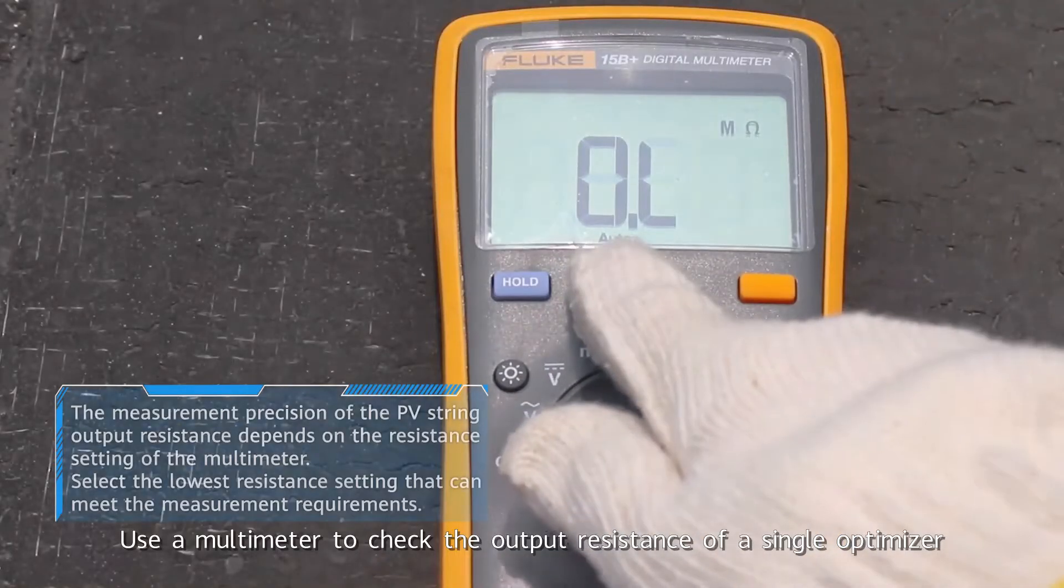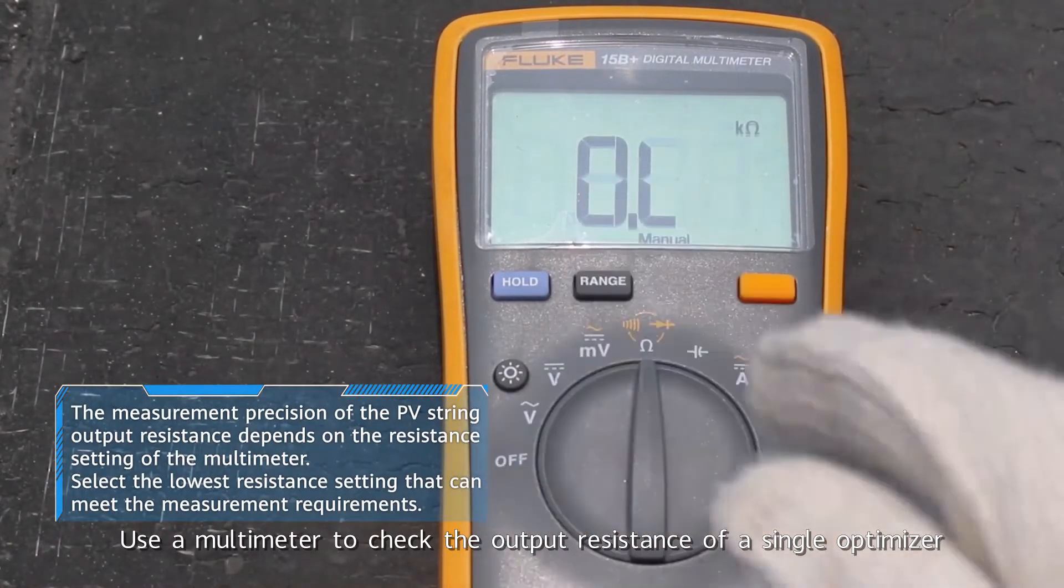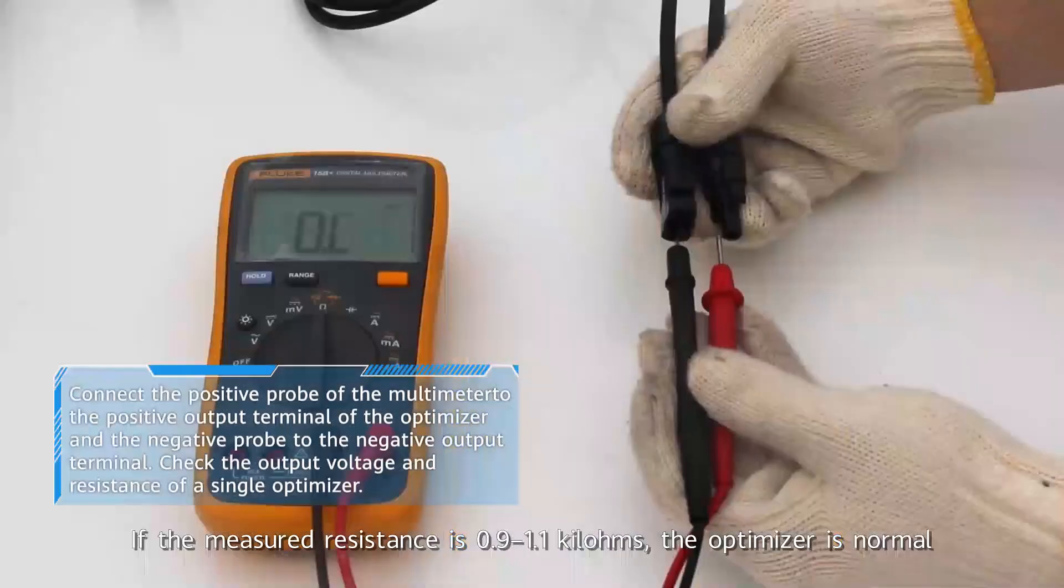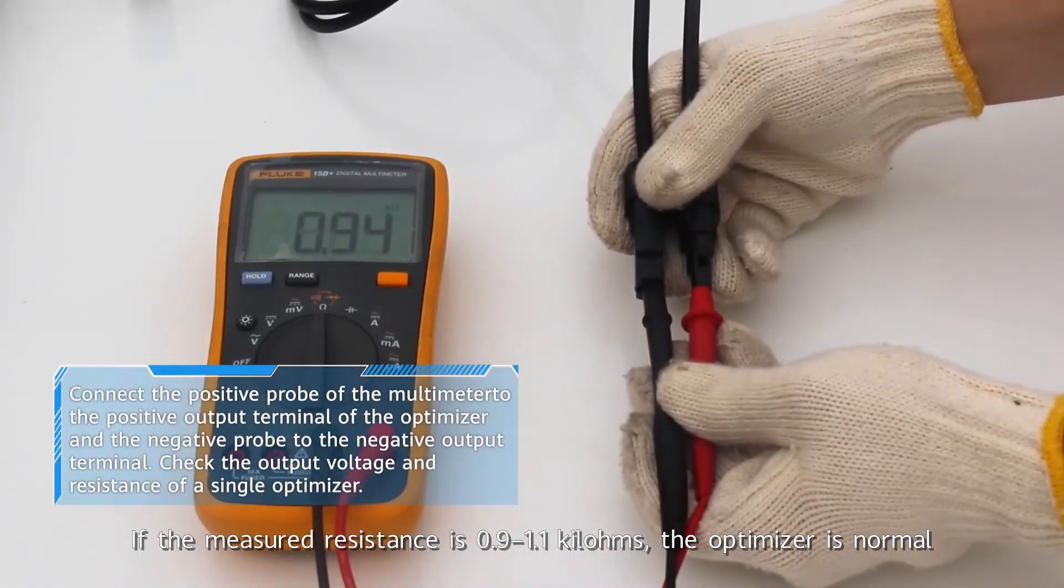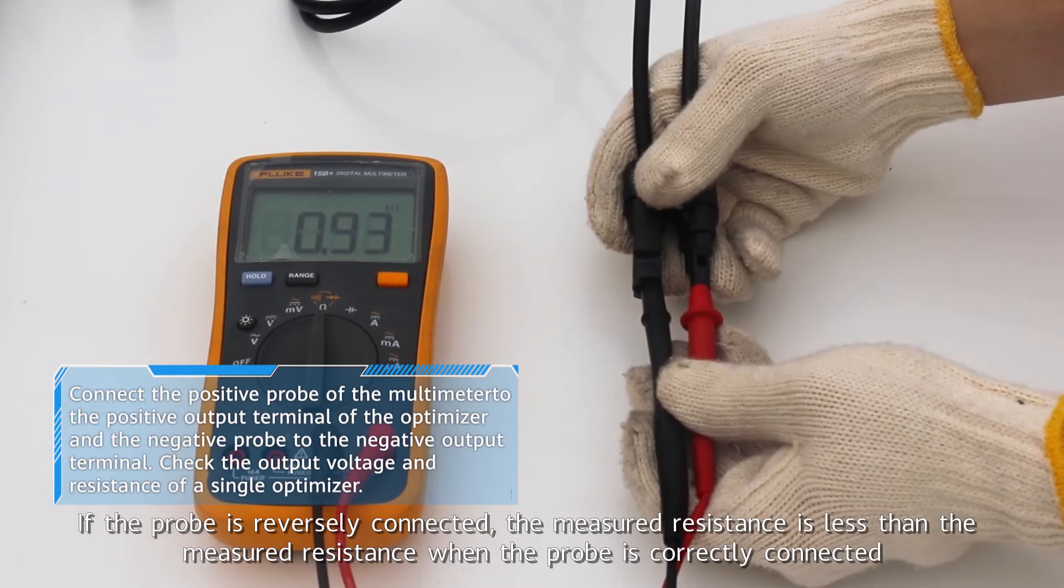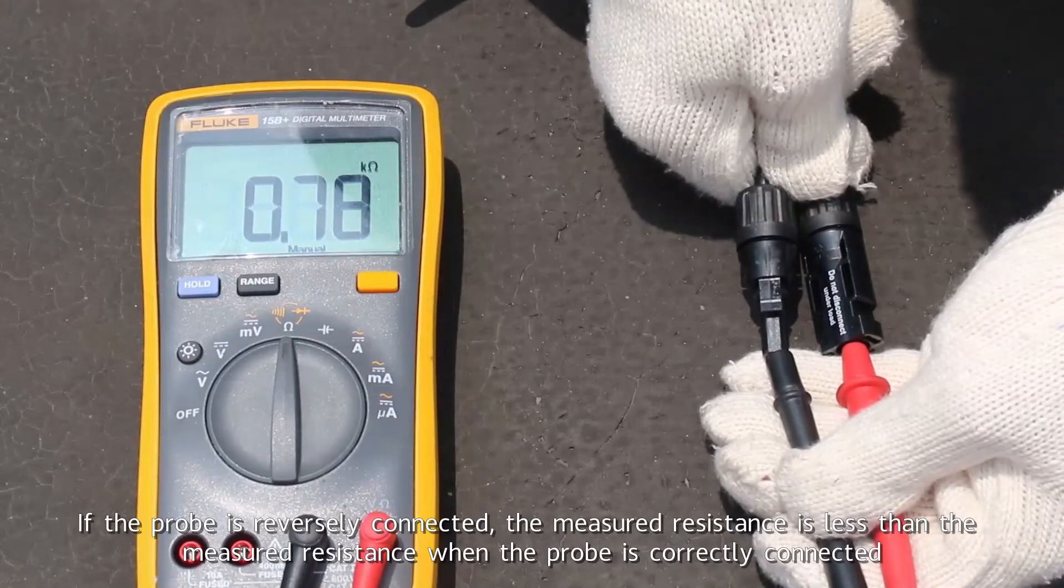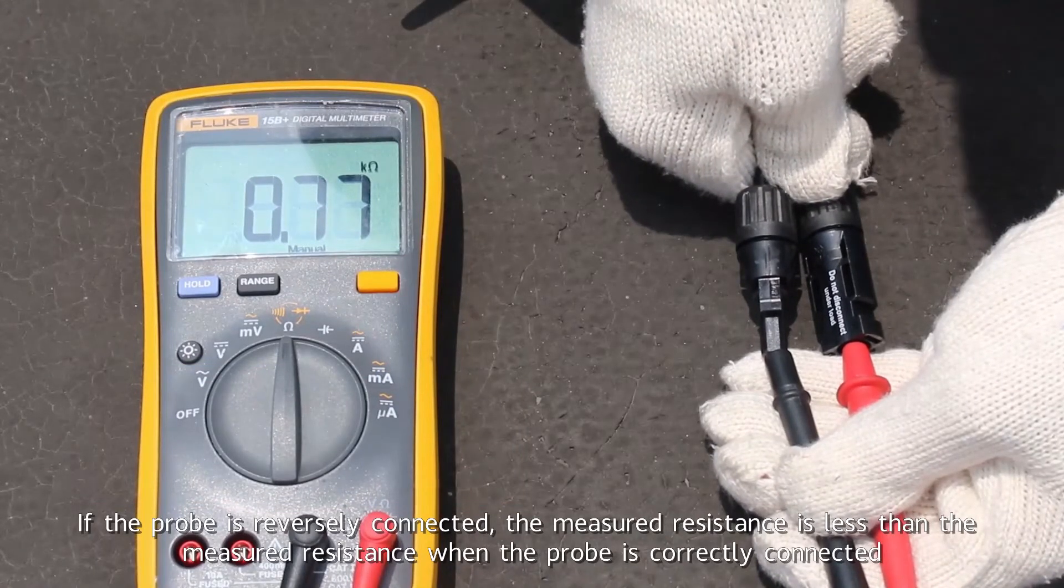Use a multimeter to check the output resistance of a single optimizer. If the measured resistance is 0.9 to 1.1 kilohms, the optimizer is normal. If the probe is reversely connected, the measured resistance is less than when the probe is correctly connected.